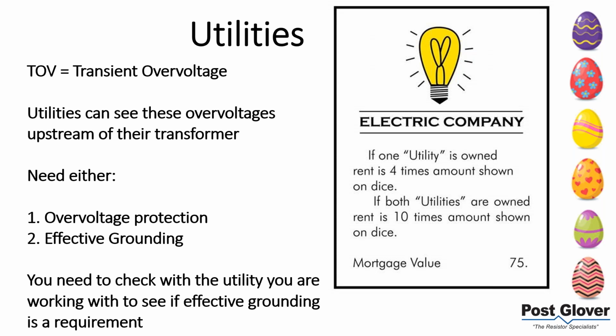So there's some examples of utilities that have some over voltage protection there, and that's how they give their customers more freedom to do what they want. But there's also utilities that, because of this point, require you to effective ground, which we just talked about. So you need to know, this is an important point. Even if technically speaking there are some benefits to achieve with resistance grounding, if your utility is not going to allow you to do that because of their protection, that's a problem. So I just want to make sure you guys are aware of that. You need to check to see what they require.